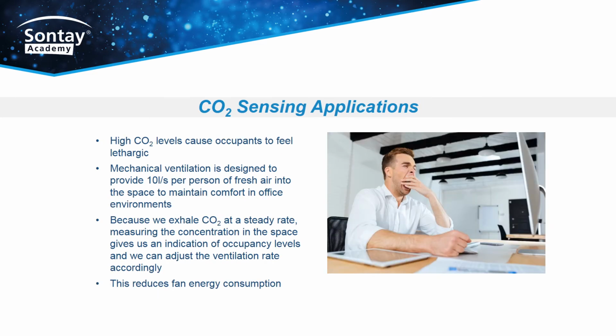CO2 sensing applications. High CO2 levels cause occupants to feel lethargic. Mechanical ventilation is designed to provide 10 litres per second per person of fresh air into the space to maintain comfort in office environments. Because we exhale CO2 at a steady rate, measuring the concentration in the space gives us an indication of occupancy levels, and we can adjust the ventilation rate accordingly. This reduces fan energy consumption.